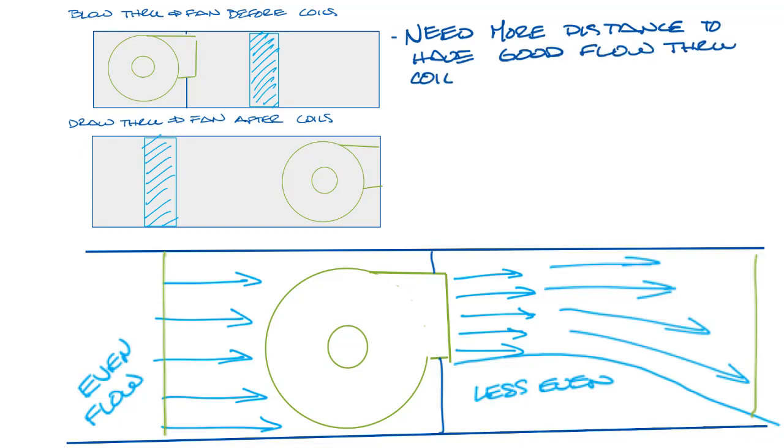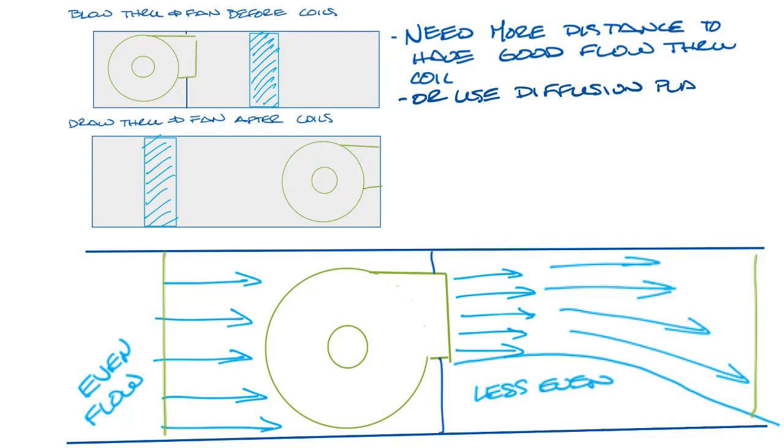You could also put a diffusion plate in between the fan and the coil to diffuse or spread out the air flow, but this will add pressure drop to the unit, and pressure drop equals energy, so this is not necessarily a better option.